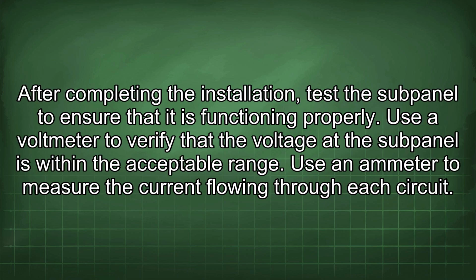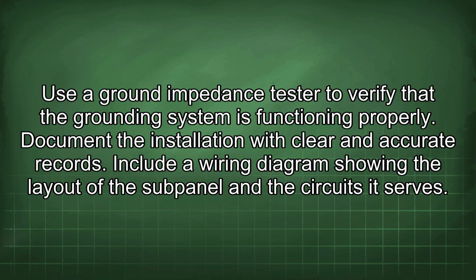After completing the installation, test the subpanel to ensure that it is functioning properly. Use a voltmeter to verify that the voltage at the subpanel is within the acceptable range. Use an ammeter to measure the current flowing through each circuit. Use a ground impedance tester to verify that the grounding system is functioning properly.